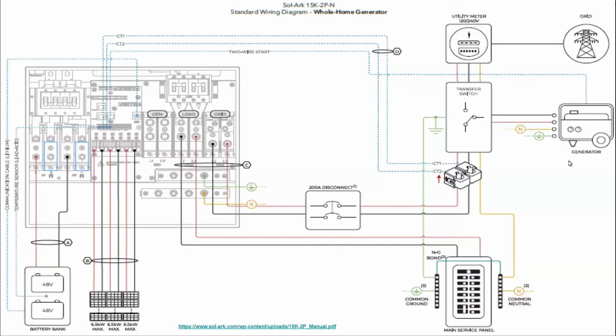Where designers start to get into trouble is when they are stacking multiple inverters, such as in luxury home design, and then putting the generator on the grid side and wanting to use the generator with peak shaving so they can run the generator to power non-backup panels and try and treat it almost like a commercial site. At that point, it doesn't always work.